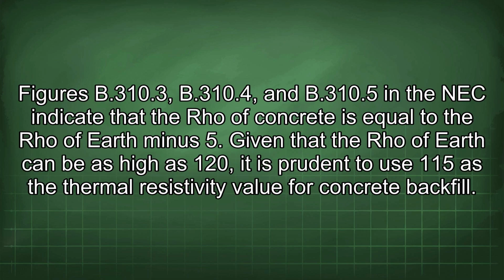Figures B310.3, B310.4, and B310.5 in the NEC indicate that the Rho of concrete is equal to the Rho of earth minus 5. Given that the Rho of earth can be as high as 120, it is prudent to use 115 as the thermal resistivity value for concrete backfill.